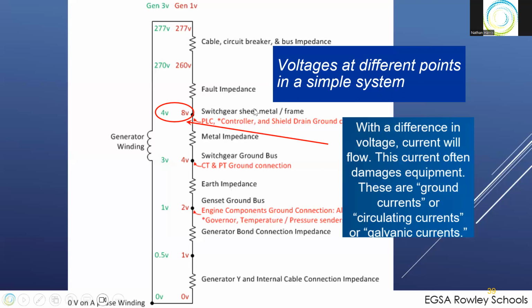So these are circulating currents or galvanic currents, unknown at the time. We now know what they are, but at the time we didn't know what they were going to be exactly. So this is the isolation that we need to have in place. And this is why galvanic isolation is so important. Some of the controller makers offer to take a less expensive approach, and they will insist upon having extremely good grounding systems such that they're exactly equal.